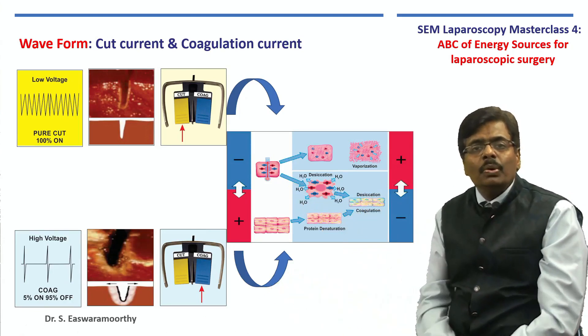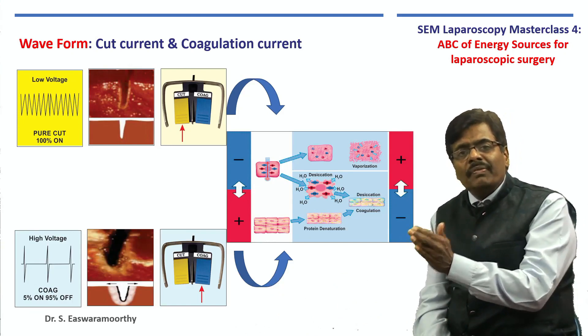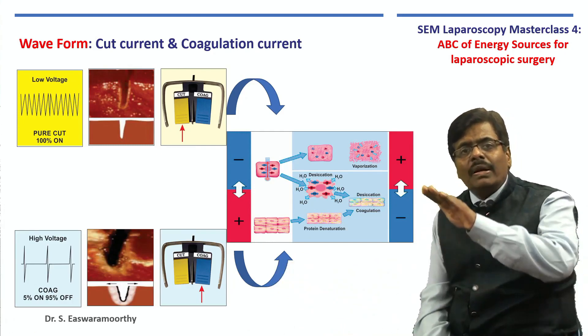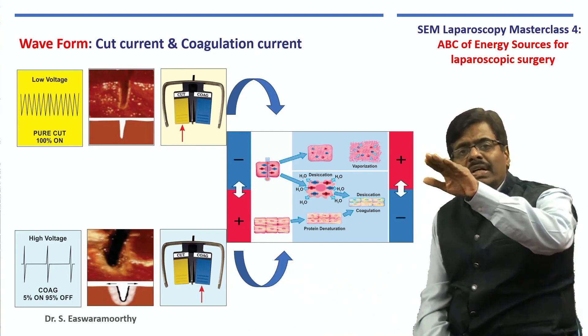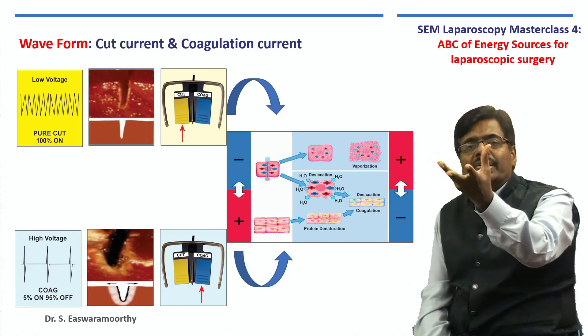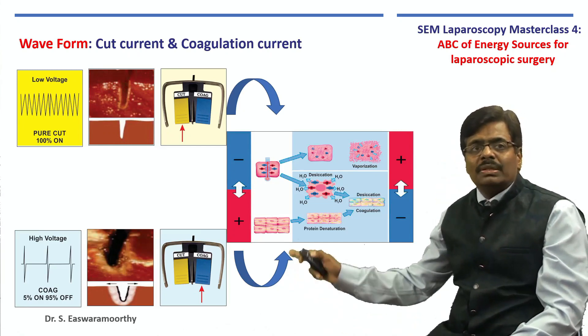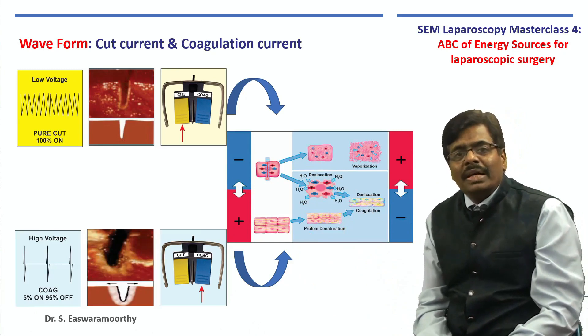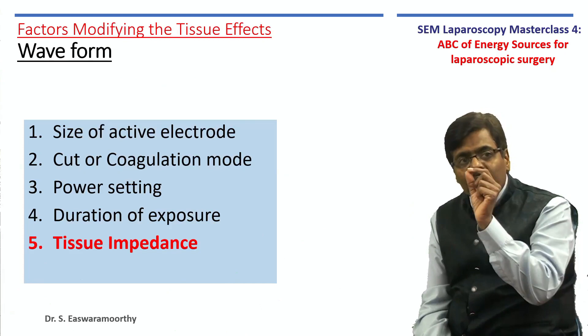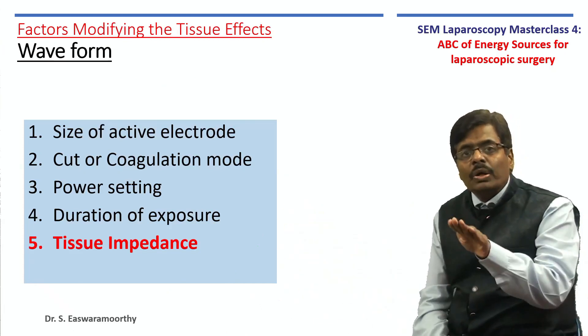We also have a via media: the blend mode, where you press the yellow cutting pedal but get blend 1, blend 2, or blend 3. In cut mode, the continuous flow of current causes a rapid rise in temperature in each cell — the water vaporizes, the cells explode, and you get a clean cut with very little lateral thermal damage. With the blue pedal, the intermittent duty cycle causes a gradual rise in temperature, so the water slowly evaporates, causing shrinkage — desiccation. Desiccation by the blue button; explosion by the yellow button — that is the basic principle of electrosurgery.